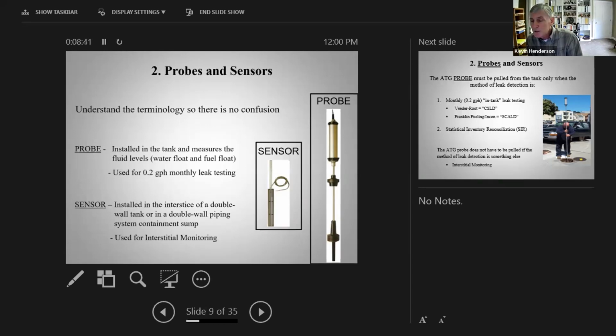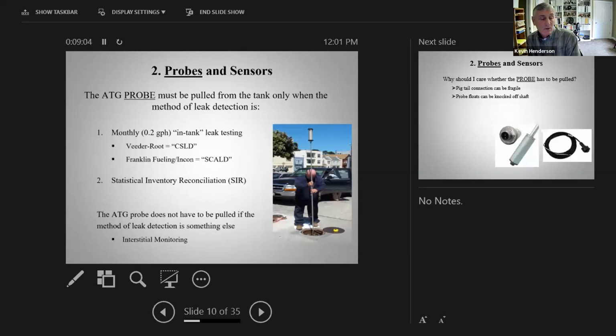So anything that is a sensor, the way that we test that and the way we look at that is different than if it is a probe. So just try to get in the habit, and it took me a while to do this myself, of calling things correctly. The probe is in the tank, the sensor is an interstitial sensor. And so we'll talk a little bit about the probe first, of course. Pulling the probe itself is not difficult, but it also can be risky. And I'll tell you what I mean by that in a minute. It is risky to pull a probe out of the tank. We don't like to do that unless we have to.